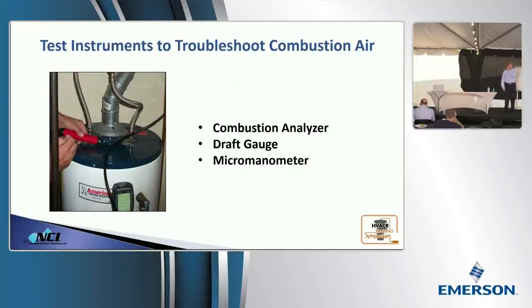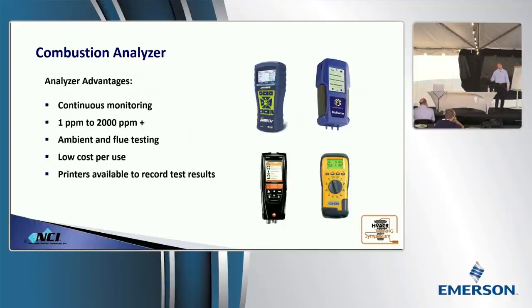Now, let's talk about test instruments. You'll notice in this list, I don't have a tape measure. And I don't have a calculator. Your number one test instrument for troubleshooting combustion air issues is going to be a combustion analyzer. If you don't have one, you need one, like yesterday. You also need two more instruments. You need a draft gauge, and you also need a micromanometer. So thank God the prices of those are coming down, because now they're affordable, fantastic testing that you can do with them. So why do we start with combustion testing?